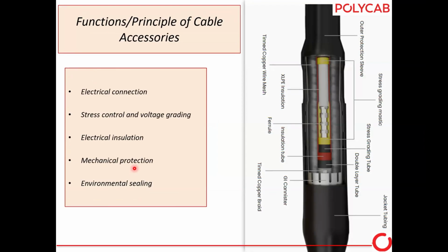So generally, I have broadly categorized the joint in 5 parts. One is electrical connection, which the joints or terminations have to do. Another one is stress controlling. The third one is electrical insulation. Mechanical protection has to be done by the canister used. And the fifth one is environmental sealing. These are the 5 functions any joint has to do.